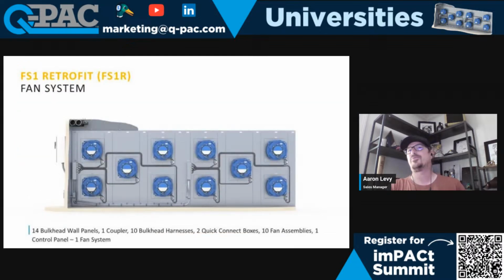This is kind of what a full system would look like when it's done. You get to see how all the connections are made from the disconnect to the quick connect boxes. In the event that you have multiple quick connect boxes, it's just daisy chained. There'll be two terminal blocks inside the disconnect — one for quick connect box 1 and one for quick connect box 2 — and all your wiring harnesses are already pre-landed for there. So that's why I probably wouldn't keep a spare wiring harness; in the event that you did have to replace one, we could get one relatively quickly.